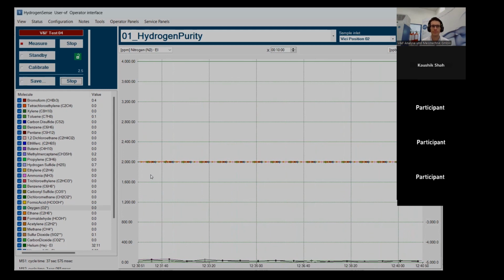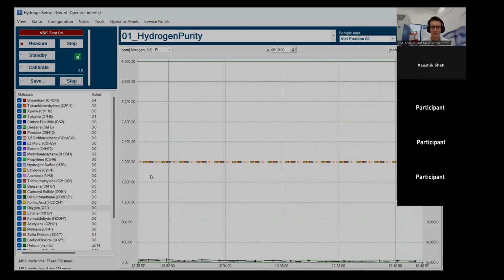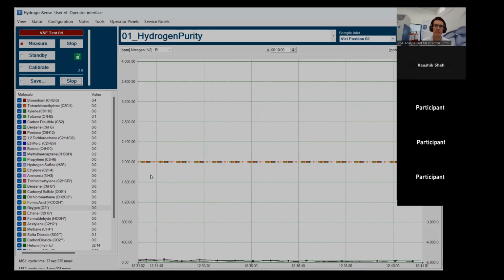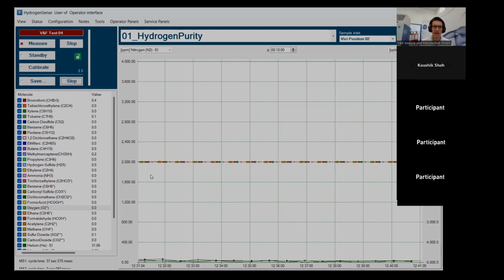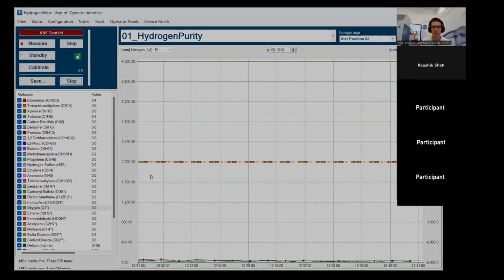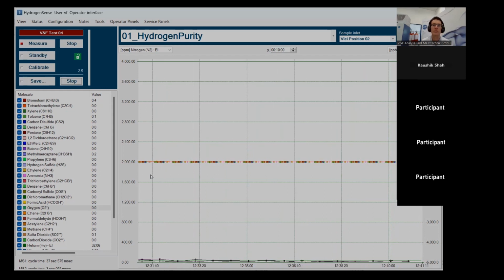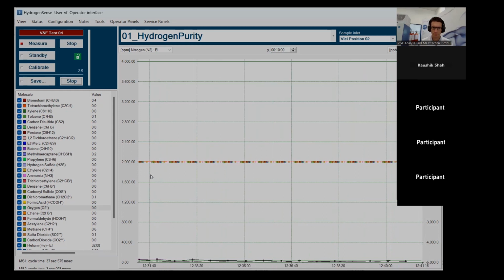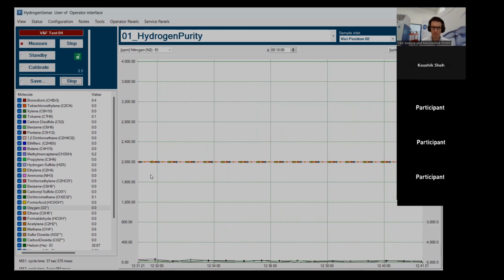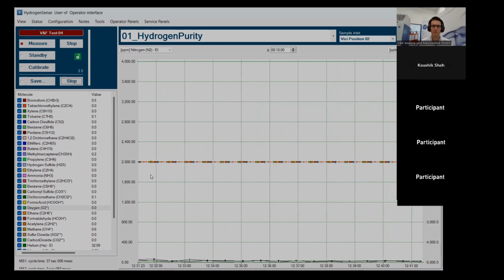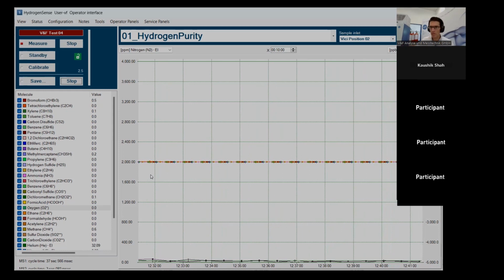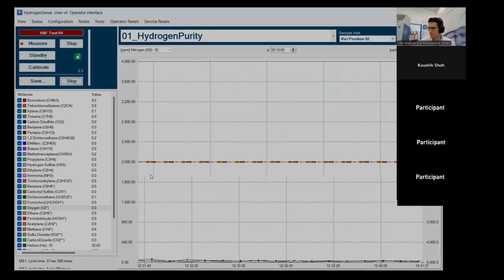Thank you. I have a doubt. Can we measure the moisture content in the hydrogen? Not on the spectrometers, but we use an auxiliary device for that. It's called MA-Tech. It's an American company. They build very highly sophisticated water analyzers. So if there is some percentage of moisture in the hydrogen, your system will not be able to detect it. There will be an auxiliary instrument in the climate cabinet which does the water analysis.